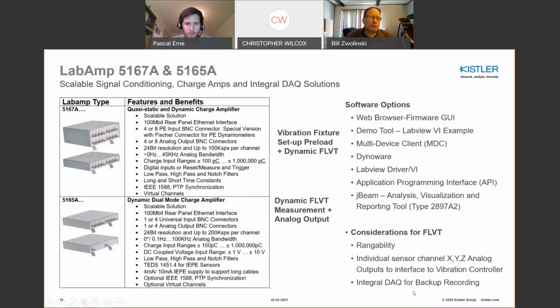So there's also other charge amps, and they're more multi-channel, digitally processed charge amps. And these here offer some fairly unique capabilities. A lot of time they've got integral data acquisition, as well as obviously performing the rangeability features that I talked to previously, which is a very important feature of using piezoelectrics. Certainly for force limiting, the rangeability is a key benefit, I think, for the measurement. You always want to allocate the dynamic range appropriately to the measurement.